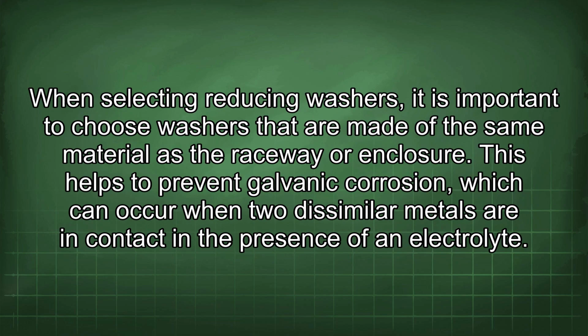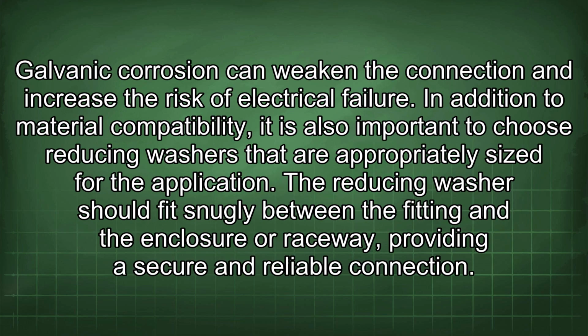When selecting reducing washers, it is important to choose washers that are made of the same material as the raceway or enclosure. This helps to prevent galvanic corrosion, which can occur when two dissimilar metals are in contact in the presence of an electrolyte. Galvanic corrosion can weaken the connection and increase the risk of electrical failure.